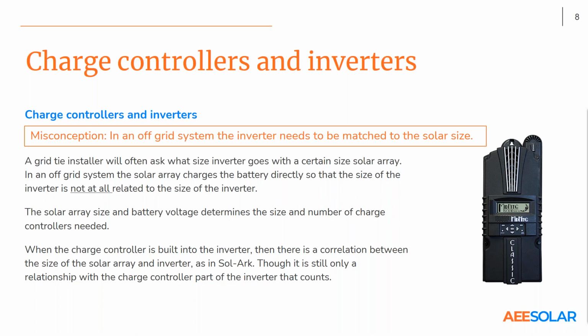What there is a correlation with is the size of the charge controller. The capacity of the charge controller is determined by the size of the solar array, and battery voltage will also have a fairly strong effect on that - we'll be looking at that. Where you have a charge controller built into the inverter, such as in a Sol-Ark, then you do have a correlation, but only with the charge controller part of the inverter. So you have to match the charge controller to the solar array, not the inverter.